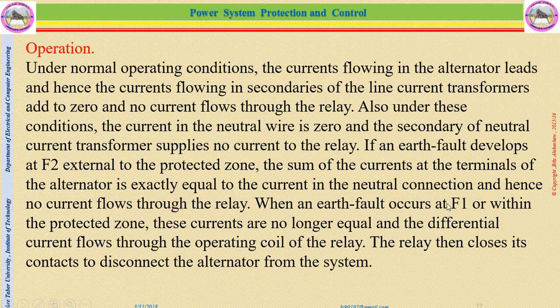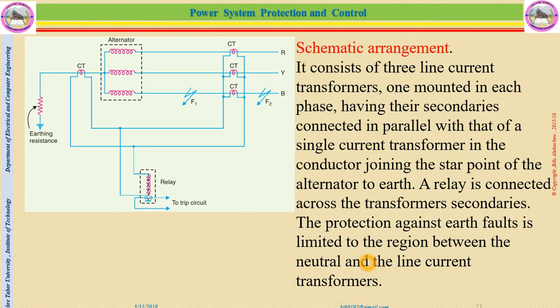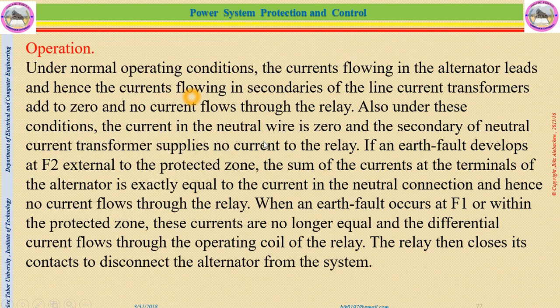When an earth fault occurs at F1 or within the protected zone, those currents are no longer equal, and the differential current can flow through the operating coil of the relay. Then the relay closes its contact to disconnect the alternator from the supply system. So this is based on the protection zone. If the fault happens outside it, there is no significant difference in the relay coils, so it does not trip. But if the fault happens in the protective zone, that means at F1, it will protect automatically.